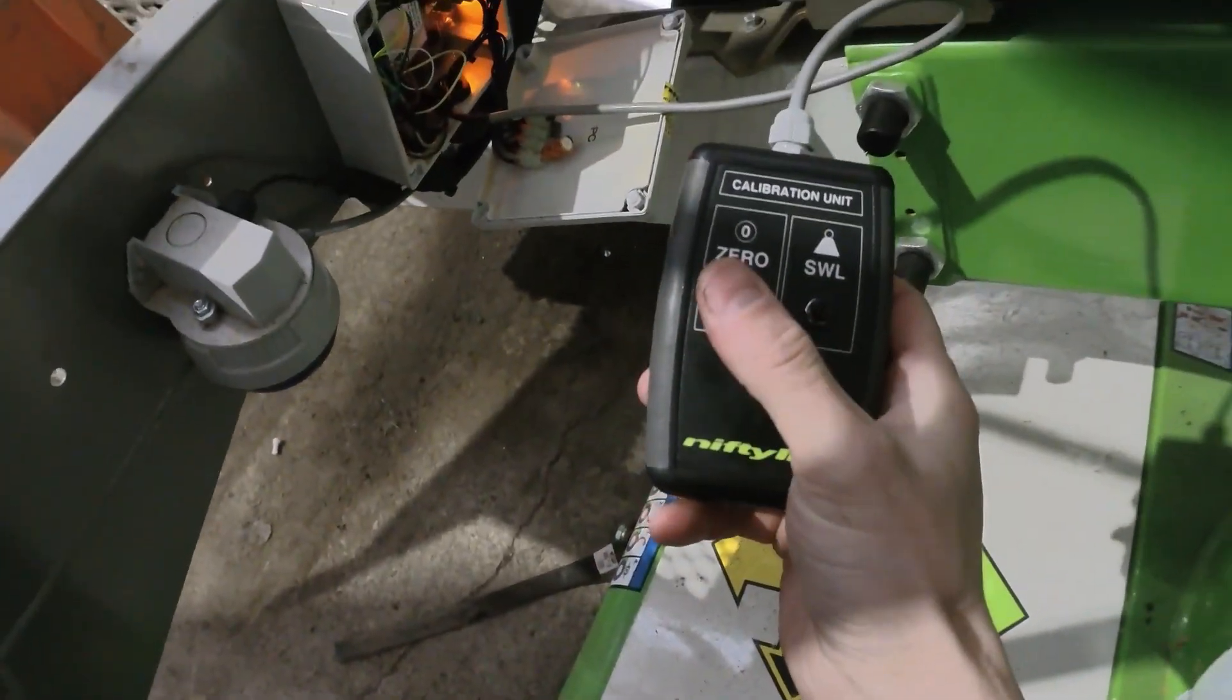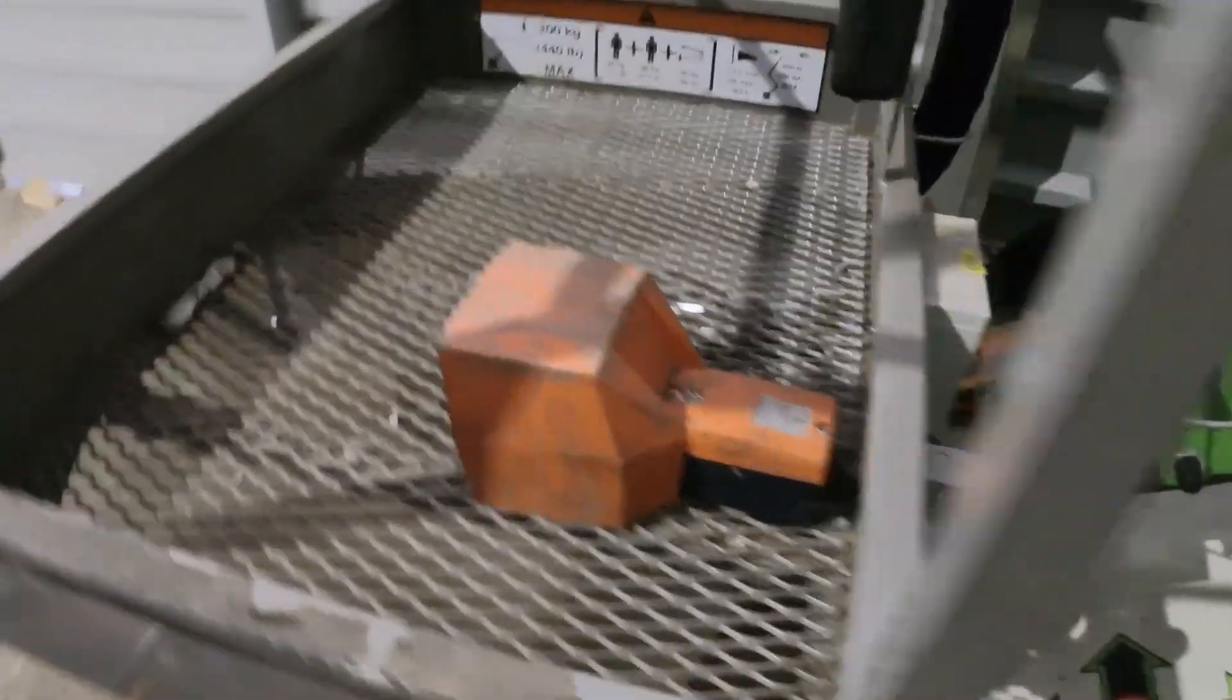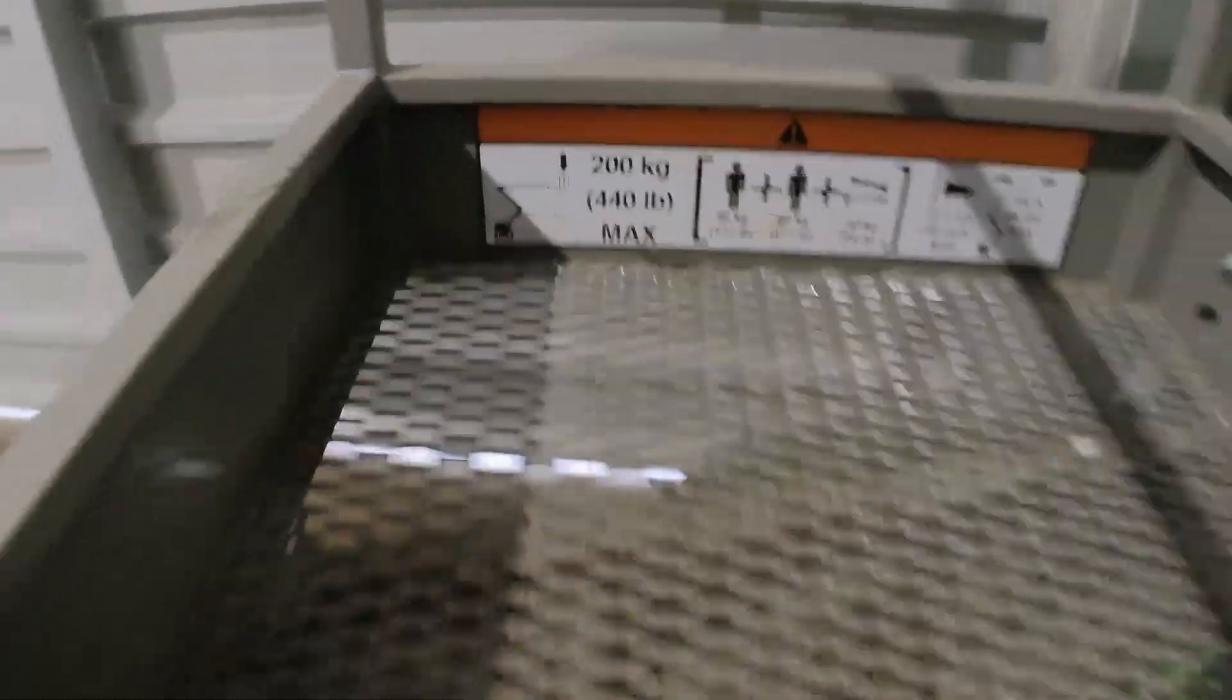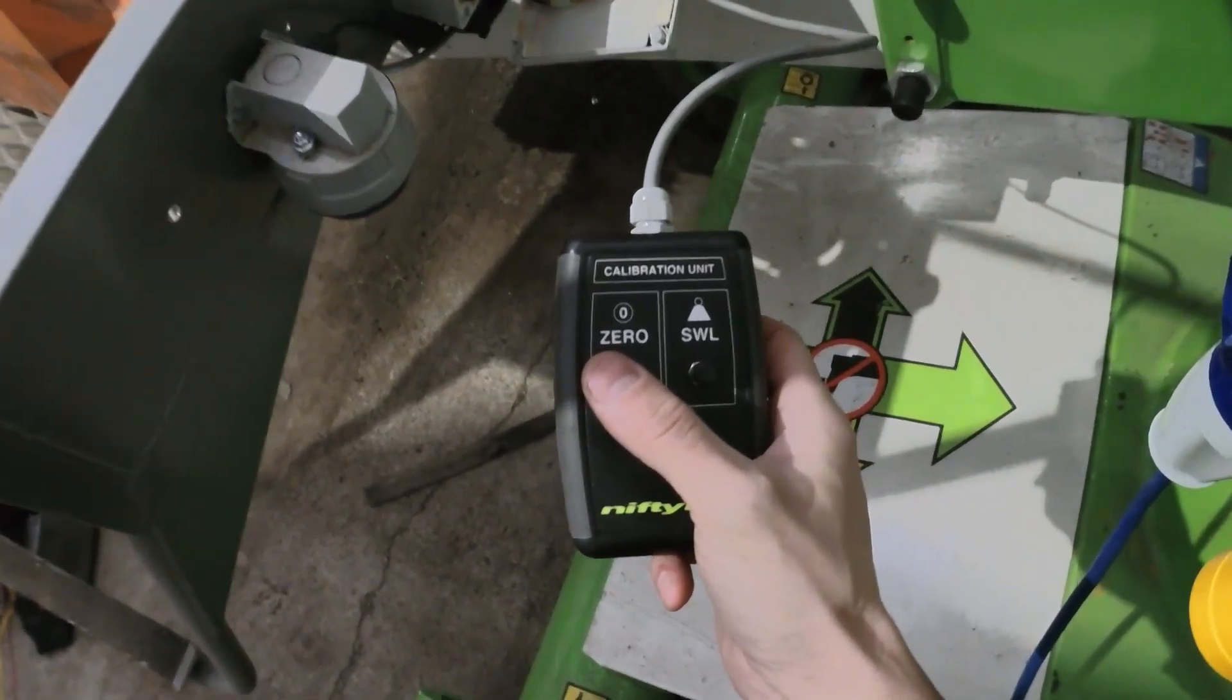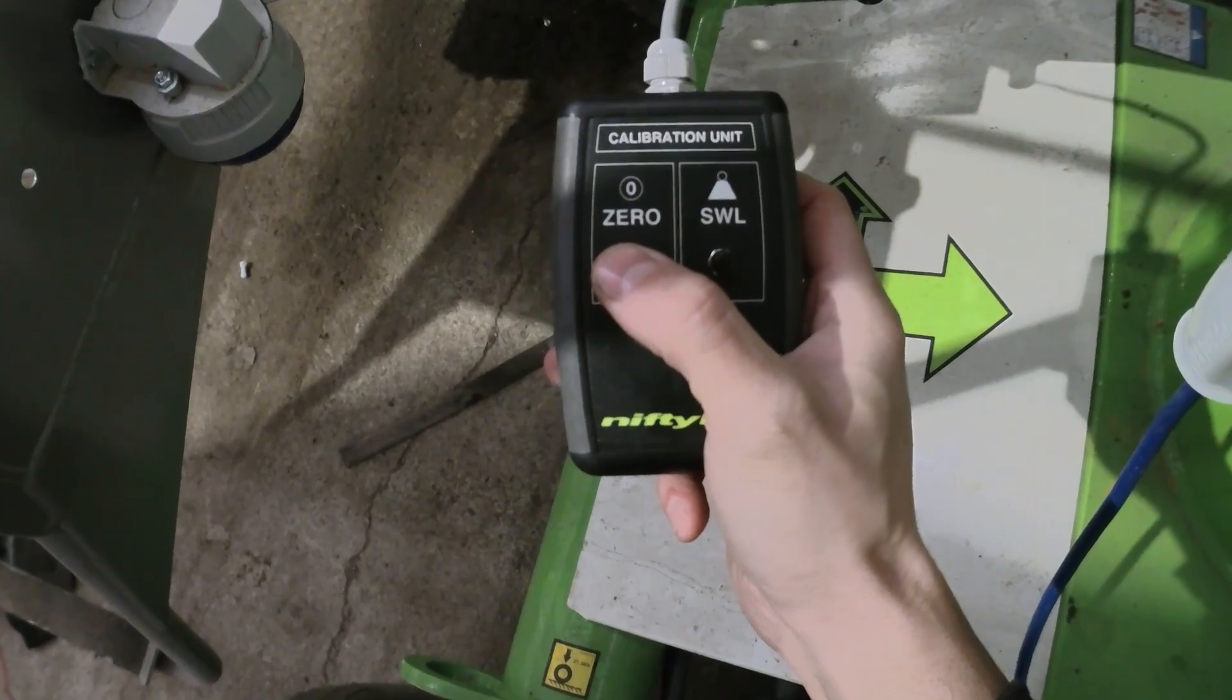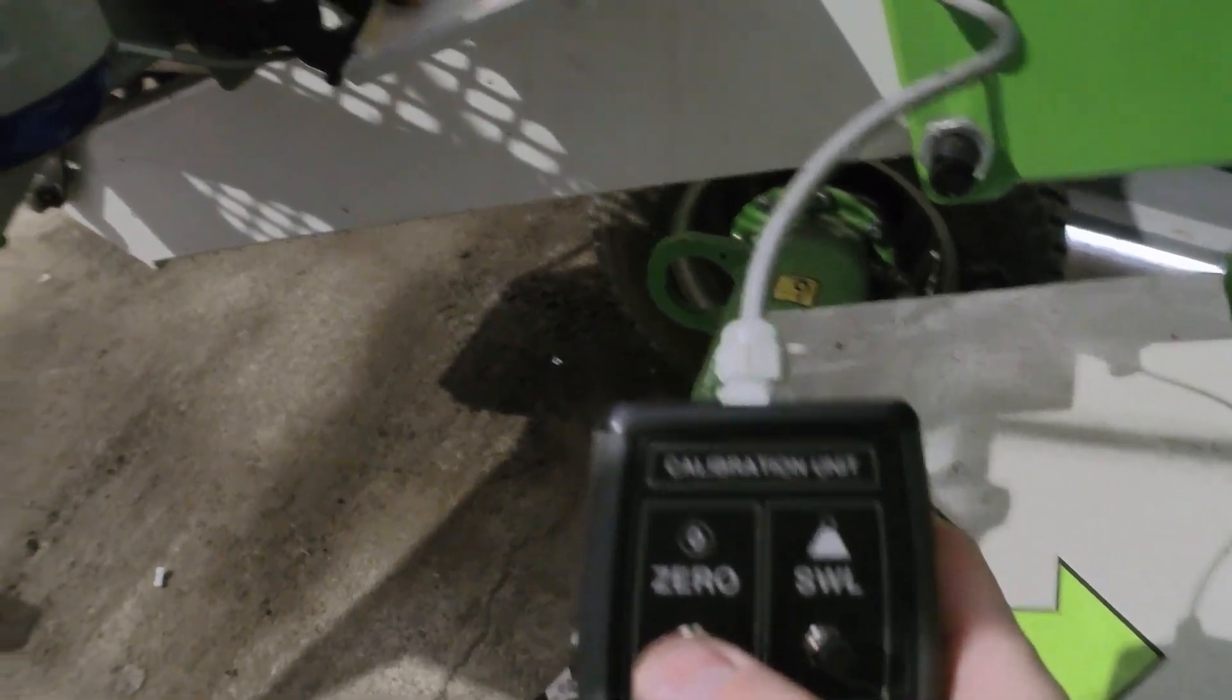First thing, as always, I will calibrate zero. We have nothing in the cage. Safe working load for this machine is 200 kilos. I will do zero with empty cage. You just need to make sure that you don't rest yourself on the cage and nothing is touching the cage, and we press and hold that for about seven to ten seconds.